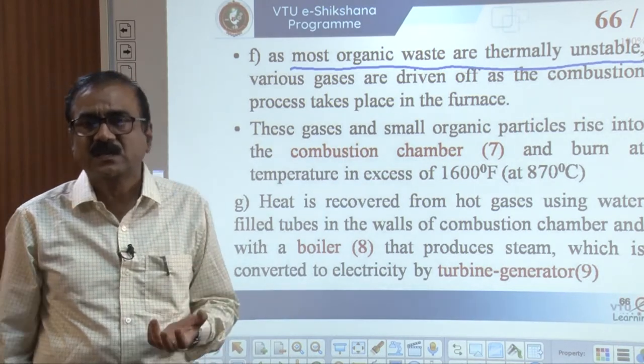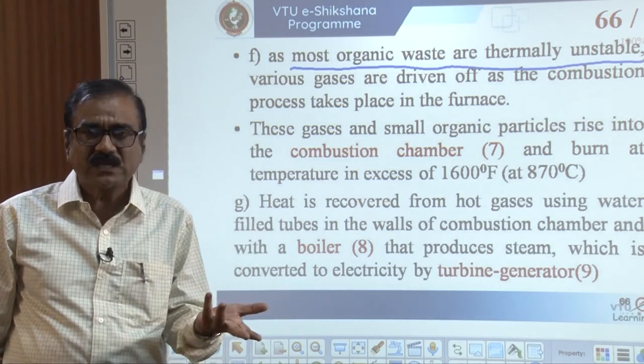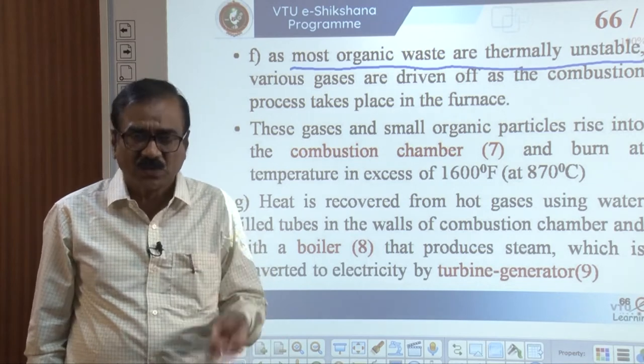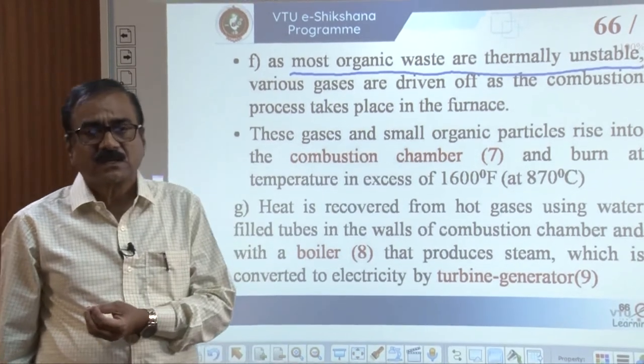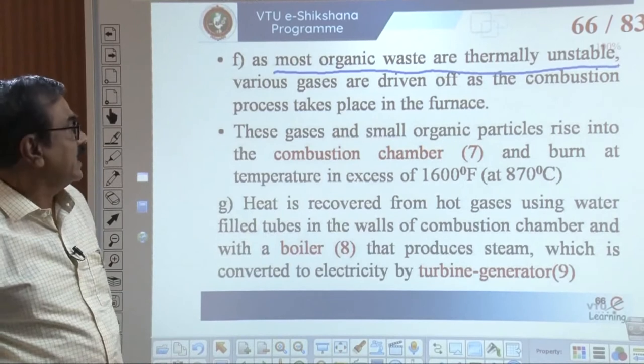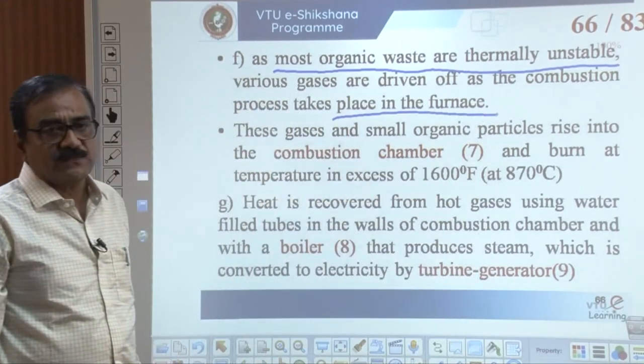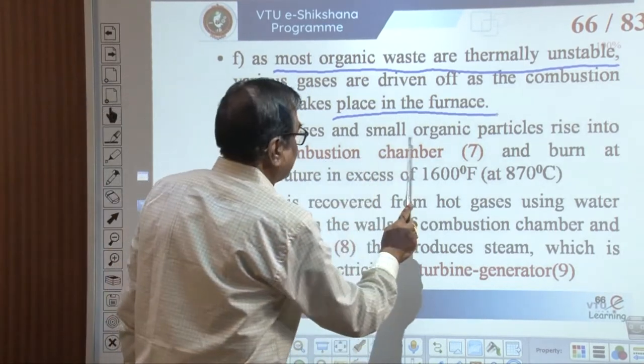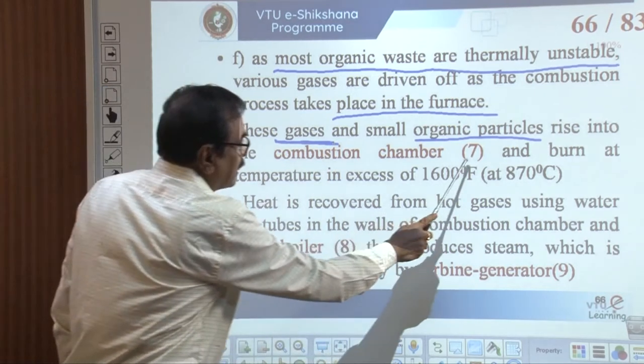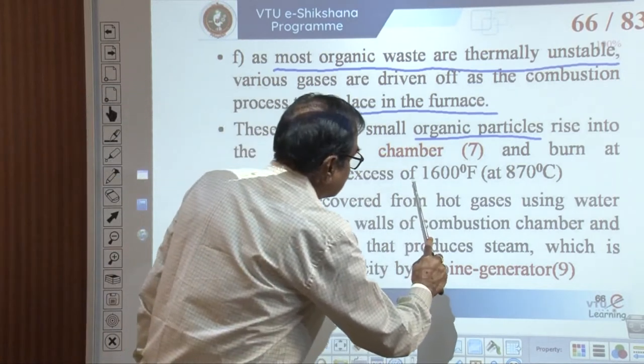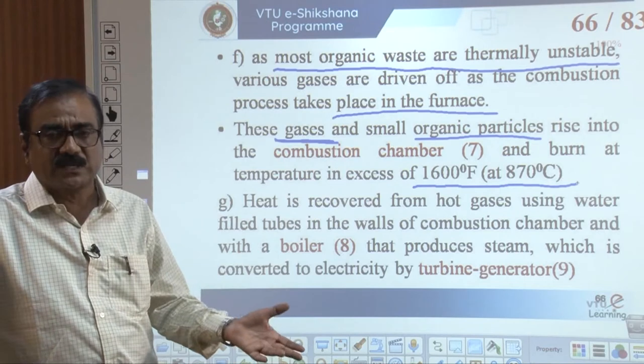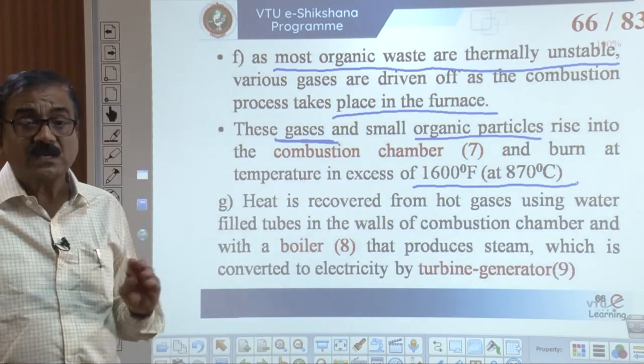Most organic wastes present in municipal solid waste are thermally unstable. When they are burnt, various gases are produced because there are many organic fractions rich in nitrogen, sulfur, and other chemicals. Depending on that, various gases are driven off during the combustion process which takes place in the furnace. These gases and small organic particles — particulate matter — rise into the combustion chamber and burn at a temperature in excess of 1600°F or approximately 870°C.